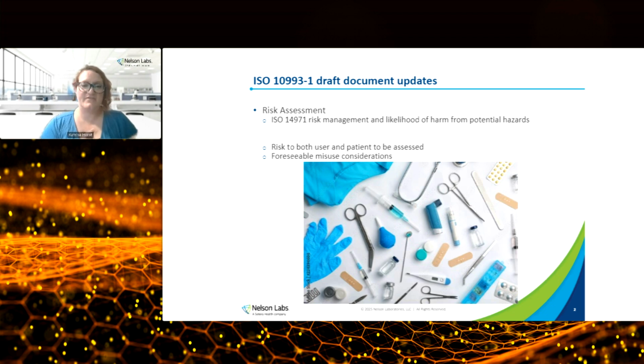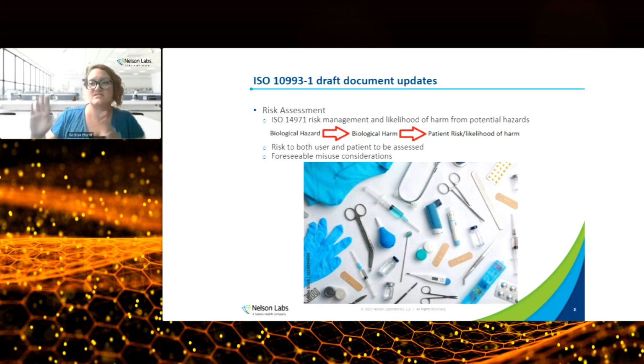The other things that are updated: 10993 has always focused on risk-based assessments. What's new is that it's bringing in ISO 14971, which wasn't really there previously. What that emphasizes, and there are several flow charts to walk you through how to do this, is the basic question: what biological hazards can we identify, what could be the harm, and then what does that mean as far as patient risk or likelihood of harm. So that's something that's new, even though to a certain degree it's always been there, but now we're actually bringing in that standard.